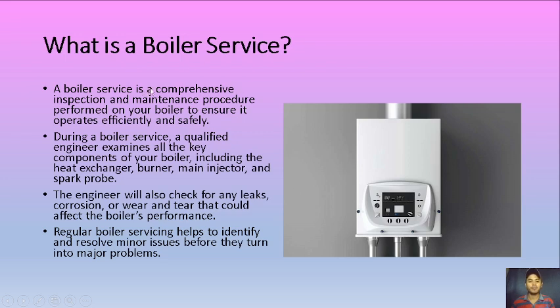A boiler service is a comprehensive inspection and maintenance procedure performed on your boiler to ensure it operates efficiently and safely. So during a boiler service, a qualified engineer examines all the key components of your boiler, including the heat exchanger, burner, main injector, and spark probe. The engineer will also check for any leaks, corrosion, or wear and tear that could affect the boiler's performance. Regular boiler servicing helps to identify and resolve minor issues before they turn into major problems. So usually when we do duty rounds, we are also checking if everything is okay on our equipment. So that's also a part of the boiler service.